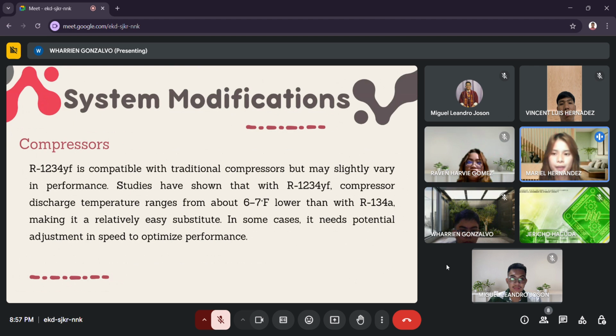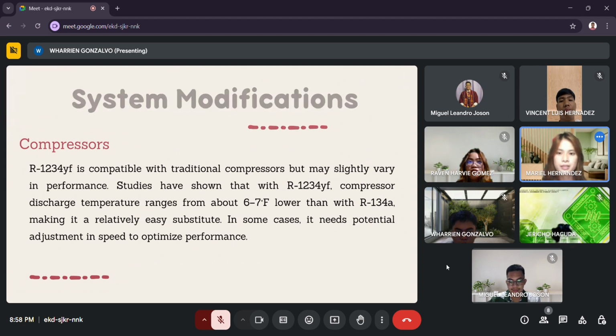Another one is the compressors. R1234yf is compatible with traditional compressors but may vary slightly in performance. Studies have shown that with R1234yf, compressor discharge temperature is about 6 to 7 degrees Fahrenheit lower than with R134a, making it a relatively easy substitute. In some cases, it needs potential adjustment in speed to optimize performance.